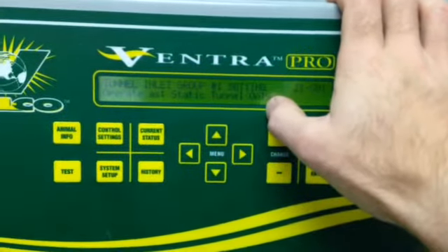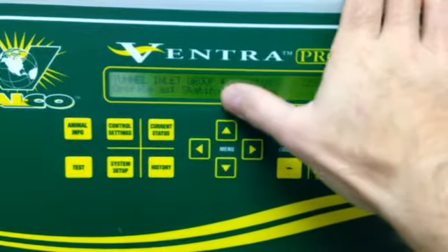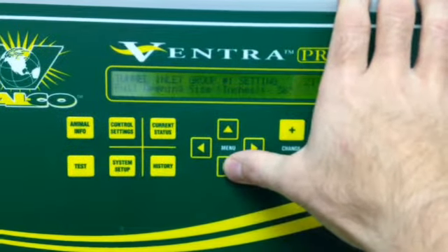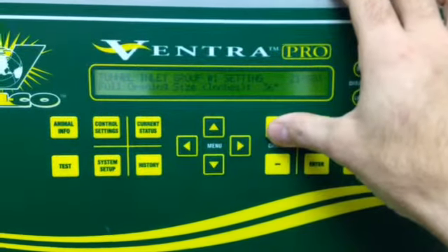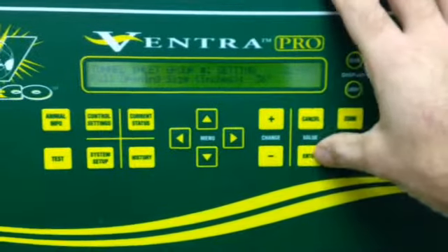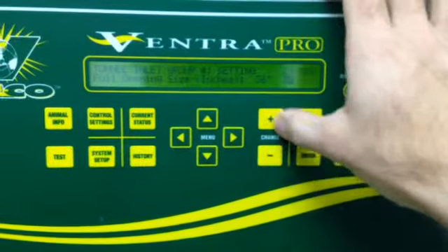This is telling us that the tunnel curtain will only open when the controller goes into tunnel mode, and once opened it will begin to operate based on the static pressure. Scrolling down through the menu, we'll see some of the other settings that will need to be verified. One is the full opening size of the curtain, in this case 36 inches, can be adjusted up or down. In our case we'll keep it at 36 inches.